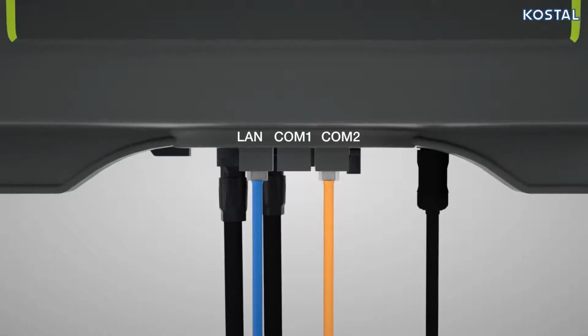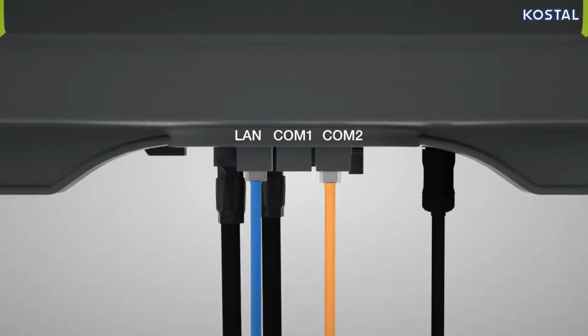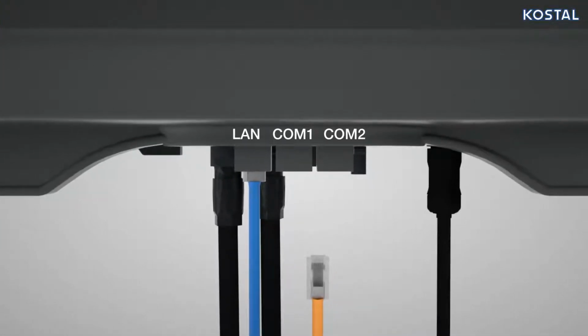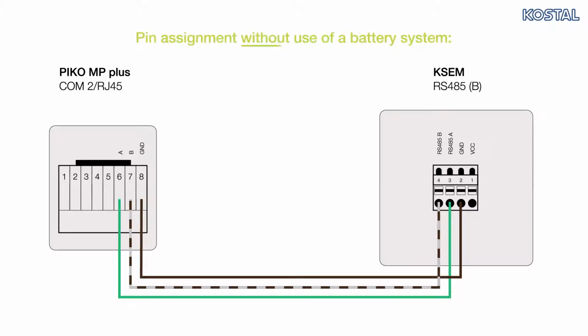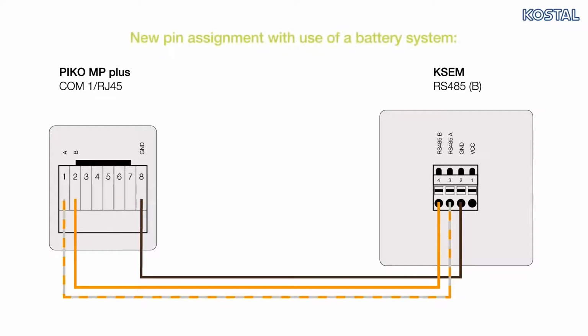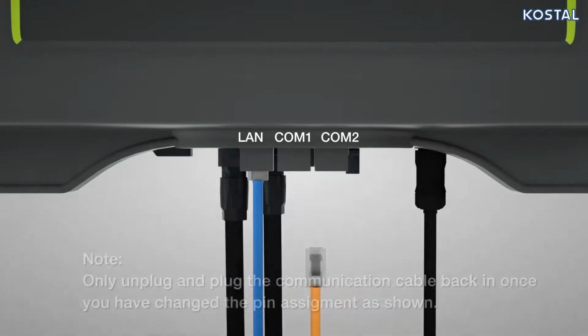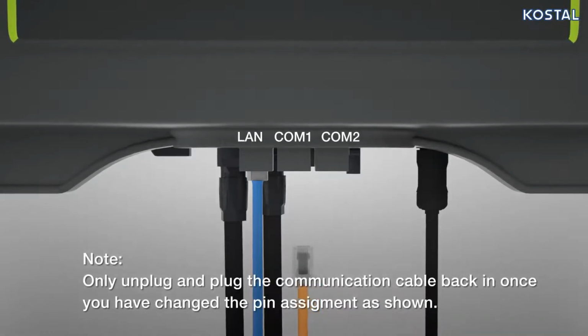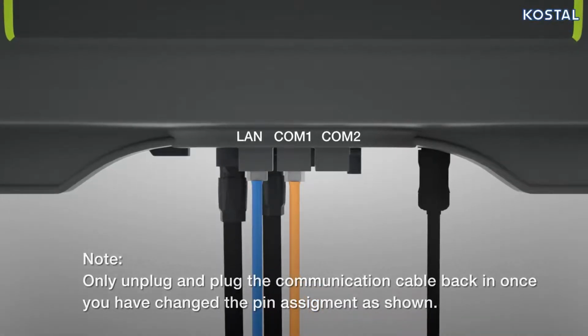Now check the communication connection between the Smart Energy Meter and the PIKO MP Plus. If you have been operating the two devices together for some time before and are only now retrofitting the battery, you will need to change the assignment of RS485 plug B on the Smart Energy Meter as shown. Please also change the COM2 connection to COM1 on the PIKO MP Plus.